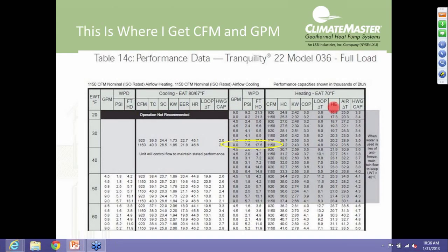So right here where it says HE, heat of extraction, these are in thousands of BTUs. Our specification, according to the engineers for this unit, is 20.9 in the case of 1150 CFM, or 20,900 BTUs, which is how many BTUs we're extracting out of the loop. Now, when we make our calculation, we hope to be within 10% of that number. If we're within 10% of that number, that unit is running just fine. If it's outside of that, then we've got a problem that we're going to have to fix. So that's how we're going to use this data to commission the heat pump.